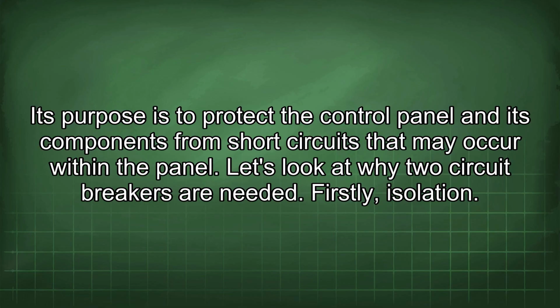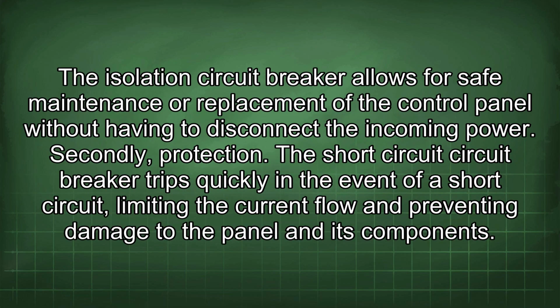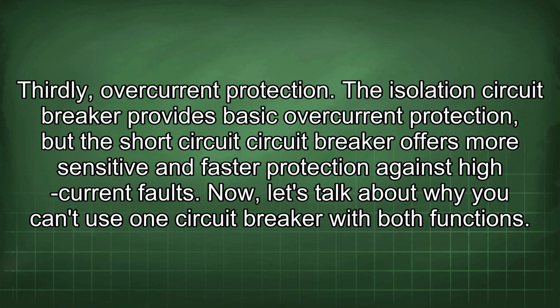Firstly, isolation. The isolation circuit breaker allows for safe maintenance or replacement of the control panel without having to disconnect the incoming power. Secondly, protection. The short circuit breaker trips quickly in the event of a short circuit, limiting the current flow and preventing damage to the panel and its components. Thirdly, overcurrent protection. The isolation circuit breaker provides basic overcurrent protection, but the short circuit breaker offers more sensitive and faster protection against high current faults.